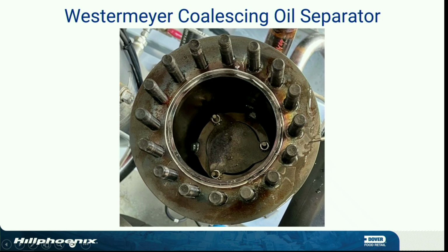It's the same as when you pull that out and that donut goes in the bottom. You don't leave it in there. You've got to go fishing and find it, right? Because if you leave it in there, where's it going to end up? If it's out, it's going to end up in your condenser. If it's outside of the separator, it can end up in that discharge line. All right? Plus, it's going to just start falling apart over time.